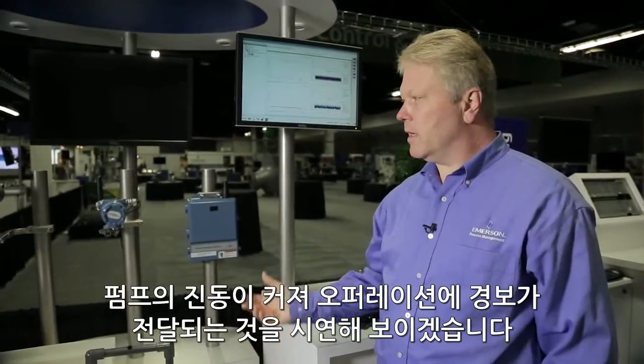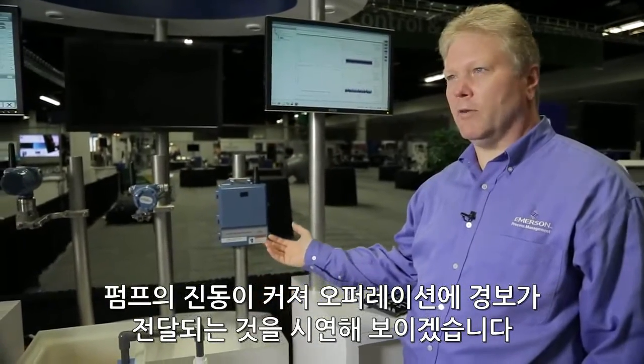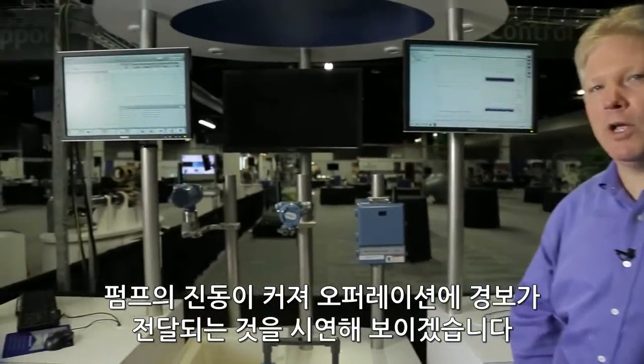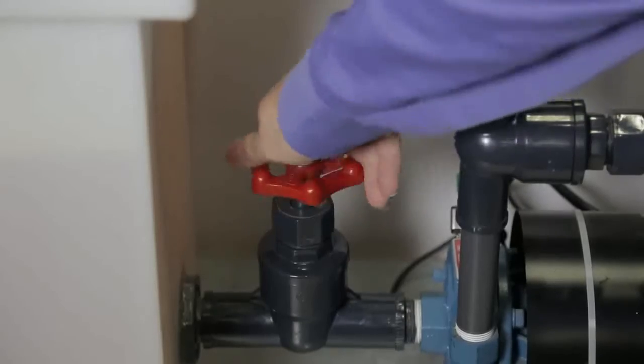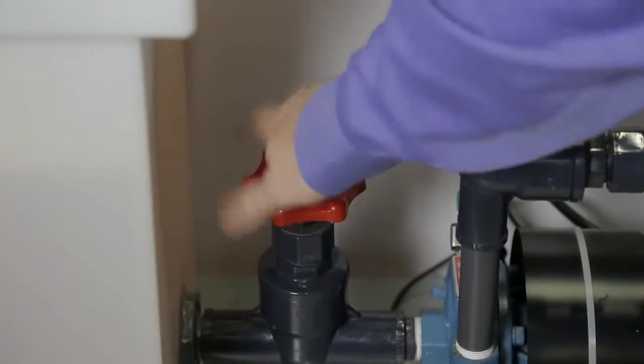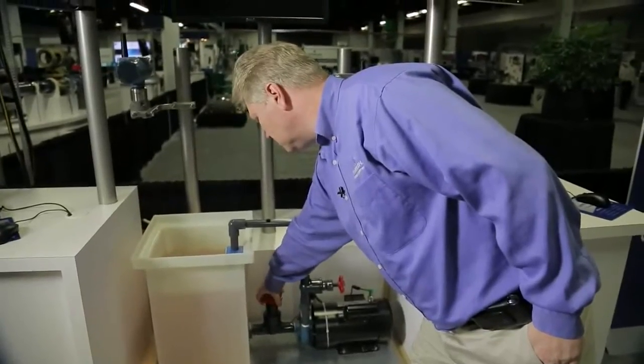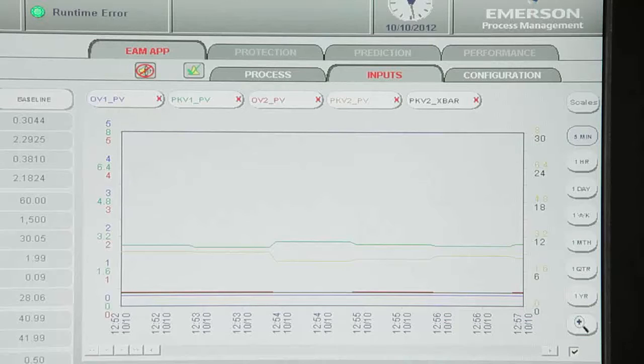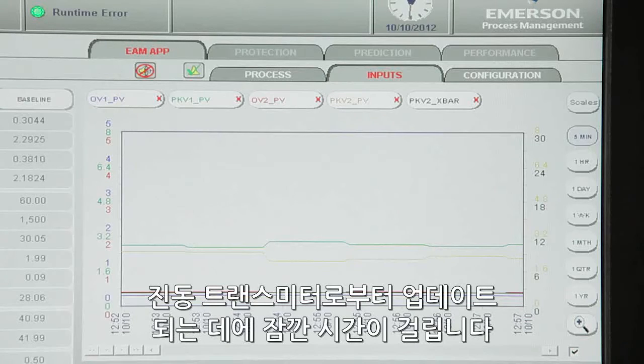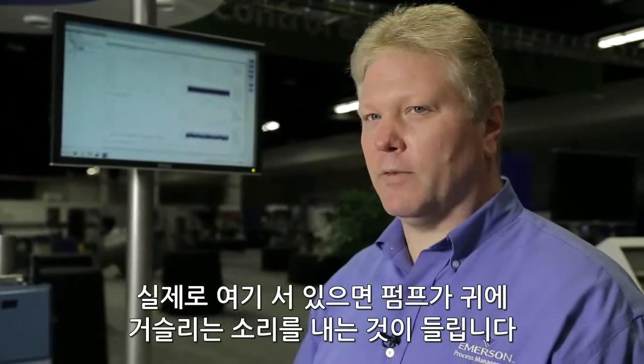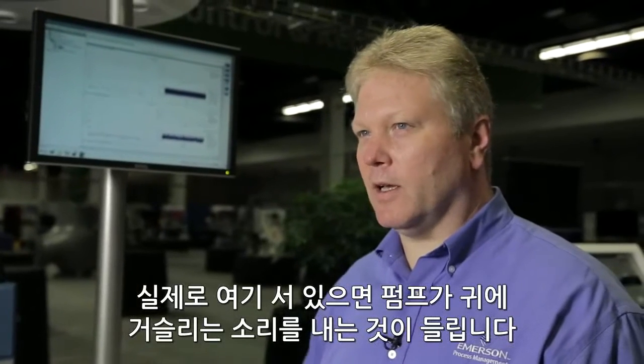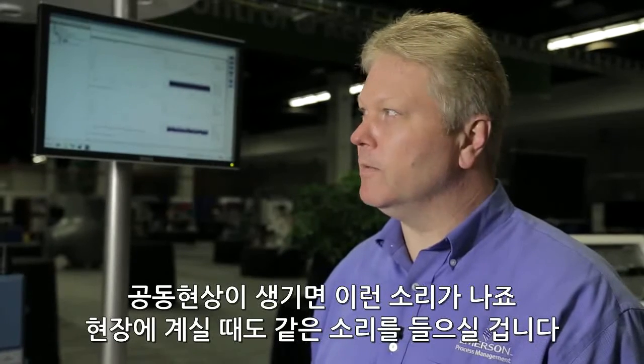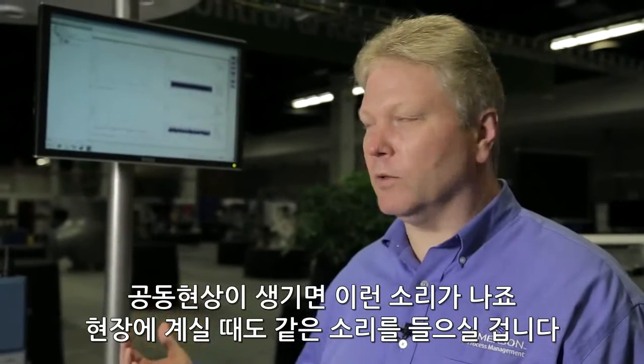And now I'd like to show a demo of cavitating the pump, in which the higher vibration will send an alert to operations. It takes a minute to update from the vibration transmitter. If you were standing here, you could hear that this pump actually sounds quite a bit like gravel going through it. That's the sound of cavitation. You would hear the same thing if you were out in the field.